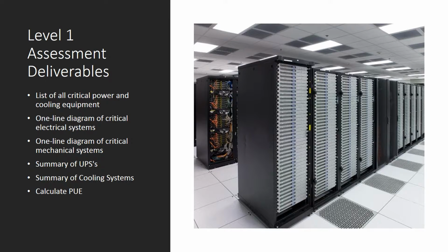Once the Level 1 assessment is complete, KNA will provide a full deliverable to the customer with all findings. This deliverable will include a list of all critical power and cooling equipment, along with a summary of all UPS and cooling systems. Also, a one-line diagram of all the critical electrical systems, along with a one-line diagram of all the critical mechanical systems, will be provided. Lastly, the PUE will be calculated and provided so the customer is aware of their ratio of the total amount of energy used by their computer data center facility to the energy delivered to their computing equipment.